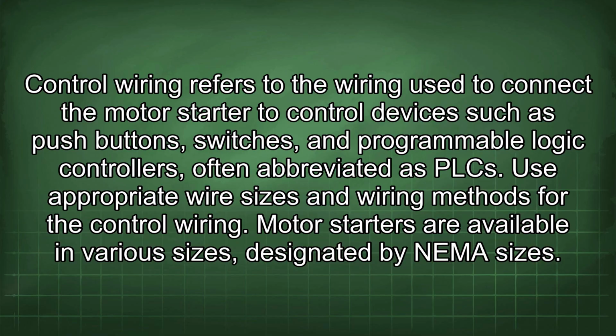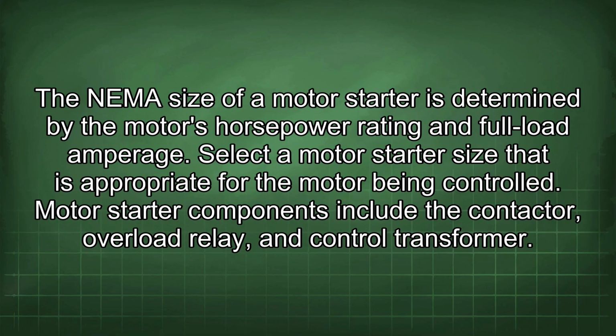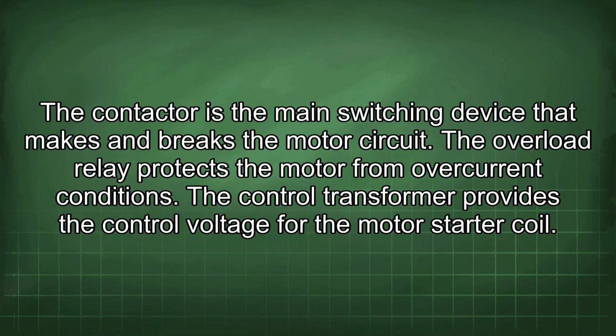Motor starters are available in various sizes, designated by NEMA sizes. The NEMA size of a motor starter is determined by the motor's horsepower rating and full load amperage. Select a motor starter size that is appropriate for the motor being controlled. Motor starter components include the contactor, overload relay, and control transformer. The contactor is the main switching device that makes and breaks the motor circuit. The overload relay protects the motor from overcurrent conditions. The control transformer provides the control voltage for the motor starter coil.